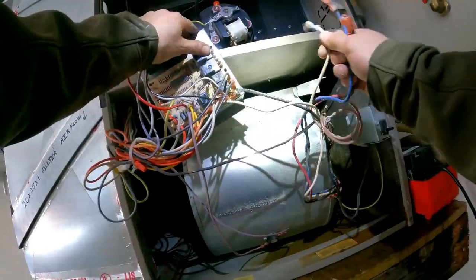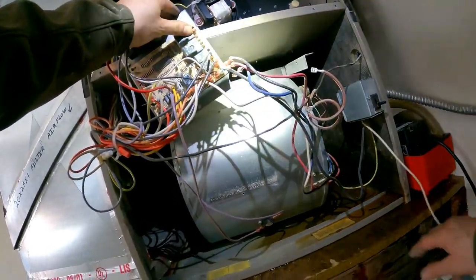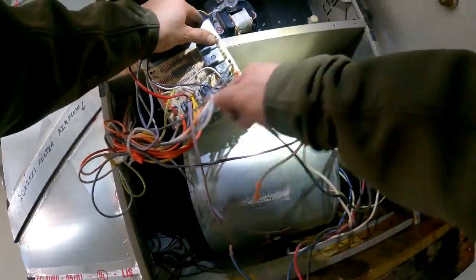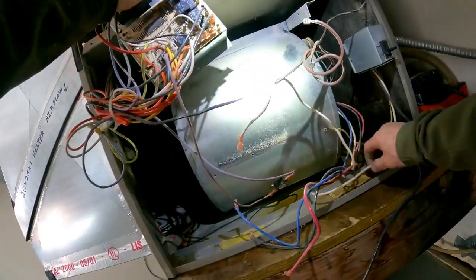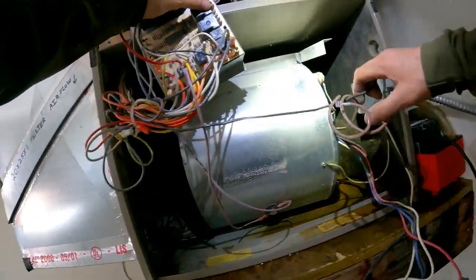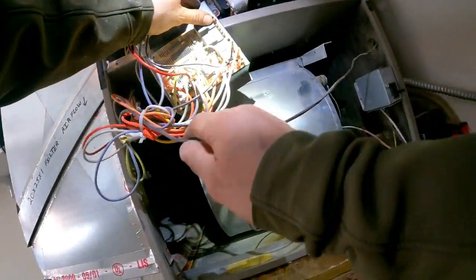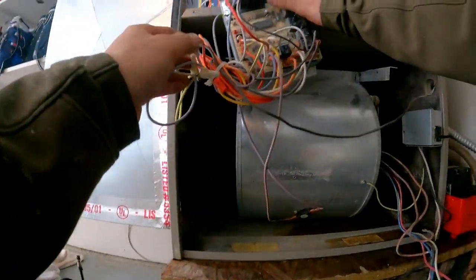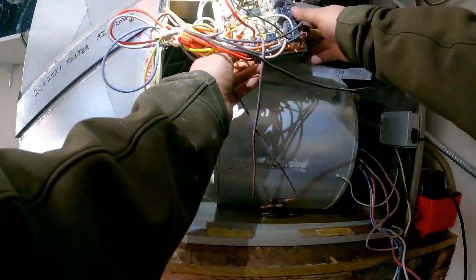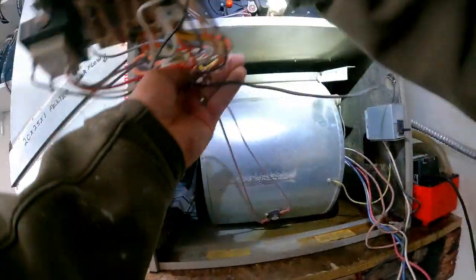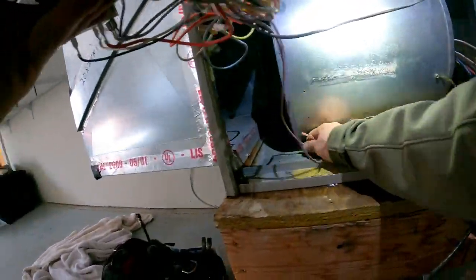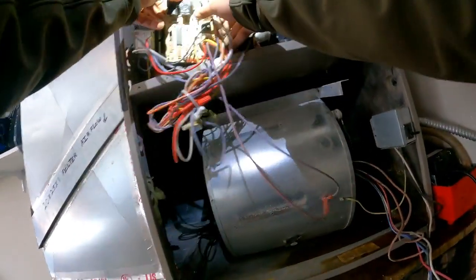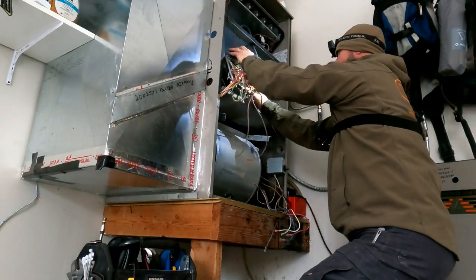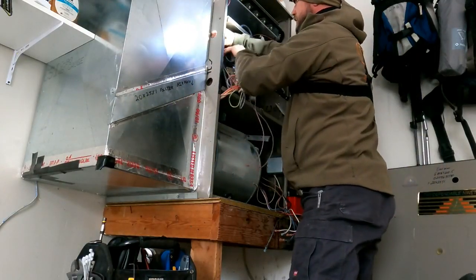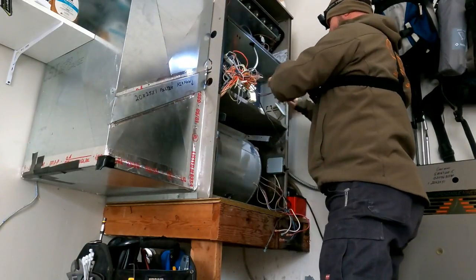Get rid of all our blower wires. My line, that's my neutral, there's that, line 2, neutrals. Now all we've got is the T-stat wire. It's wire nutted here, let's see. Get rid of my auxiliary limits - that might be enough to get it out of there. Stay, you stay.